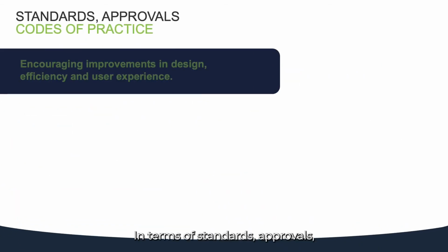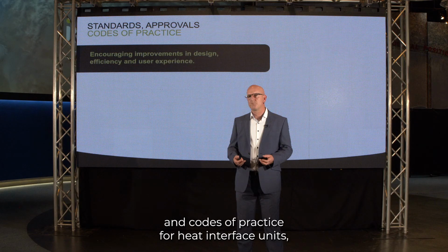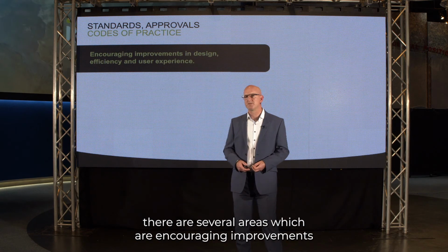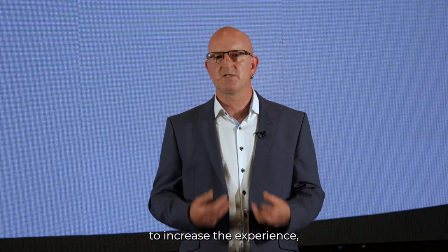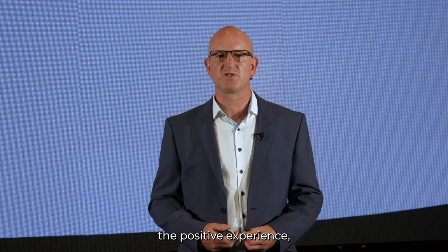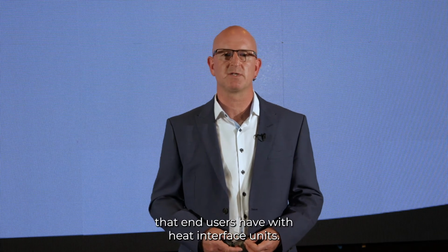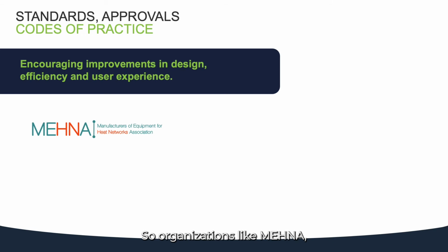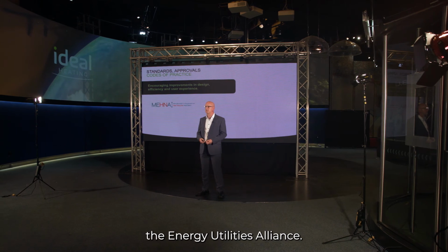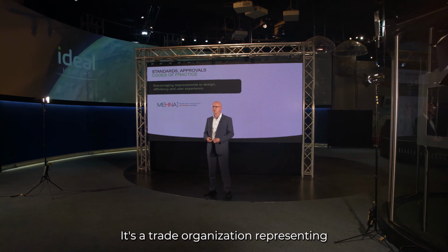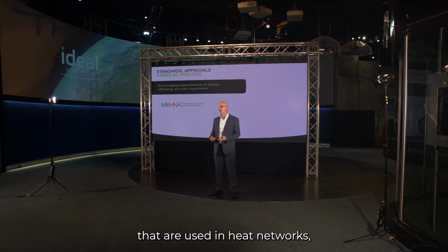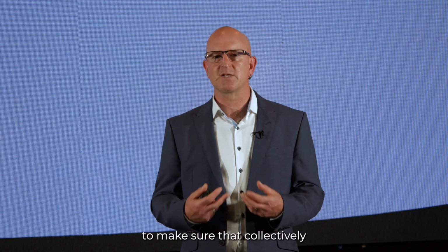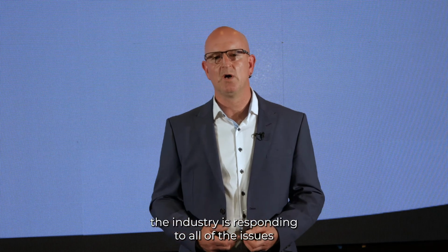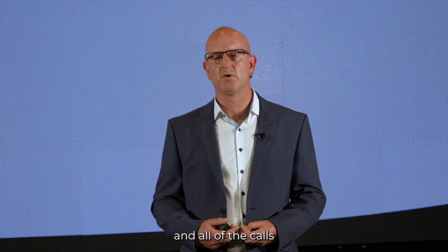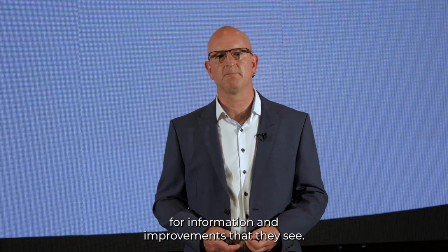In terms of standards, approvals and codes of practice for heat interface units, there are several areas which are encouraging improvements in the design and efficiency to increase the positive experience that end users have with heat interface units. So organisations like MEHNA, the Manufacturers of Equipment for Heat Networks Association, these are a group that's part of the Energy Utilities Alliance, and it's a trade organisation representing manufacturers of the equipment that are used in heat networks, to make sure that collectively the industry is responding to all of the issues and all of the calls for information and improvements that they see.